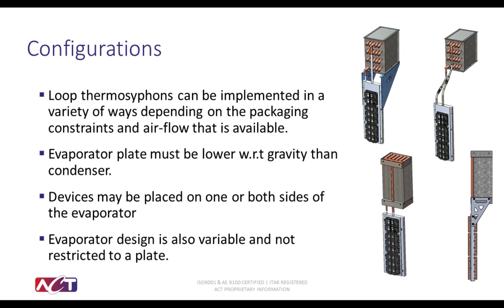The only main rule in designing a loop thermosiphon is that your evaporator must be lower with respect to gravity than the condenser. This enables the liquid head to form and passively pump your fluid through your evaporator into your condenser and have that cycle repeat. The evaporator design is also variable and not restricted to a plate form factor. Devices placed on one side and or both sides will operate in the same exact way.